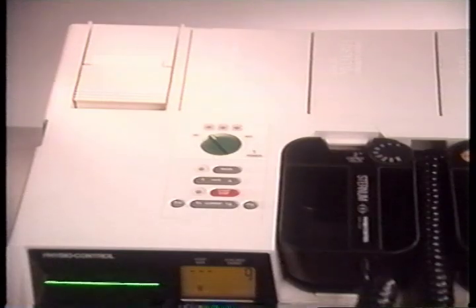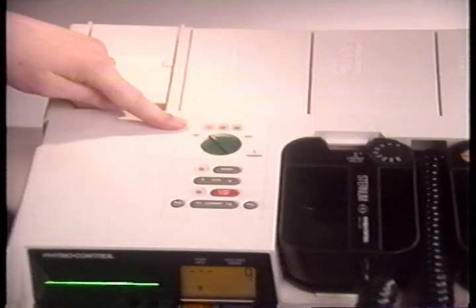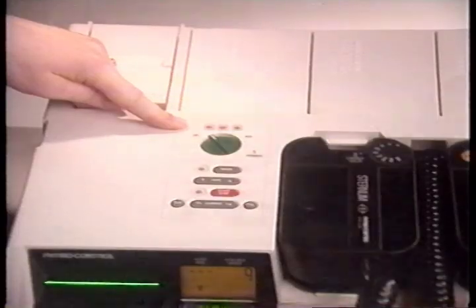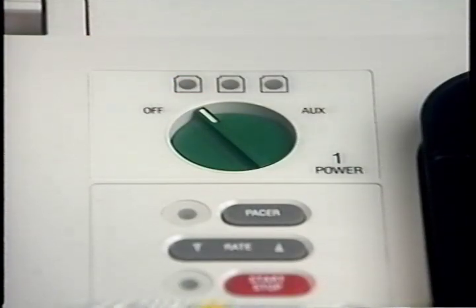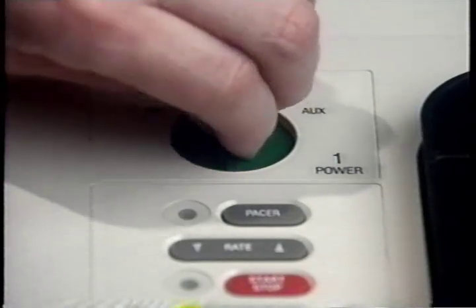Generally, a battery with 100% capacity will allow the LIFEPAK 10 to monitor for approximately 45 minutes. When the battery charge is depleted, the low battery light will illuminate above the power switch and 3 short tones will sound. Always carry spare, fully charged batteries for prompt replacement of a depleted battery.